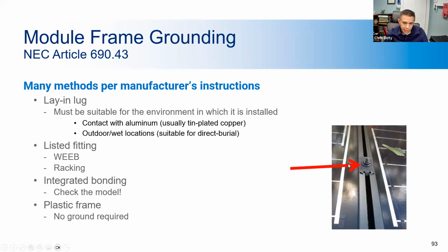Here we see an integrated mid clamp that provides the bonding of all modules, except for in this situation, there was a single module placed by itself utilizing only end clamps. So additional bonding methods would need to be employed to ensure bonding and grounding of that separate module, but throughout the main array, these would be sufficient. And there are other methods such as WEEB washers or star washers that may also accomplish bonding and grounding as well, as lay-in lugs, which we'll see in a bit more detail soon.